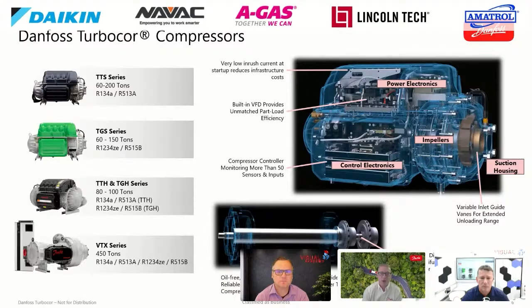Then we have the suction, with a design of twin impellers. We have power electronics on top that provide all the juice for the compressor, and control electronics on the side—this is our service side, lower voltage. You can pull that cover off, and anything that might need service or changed out in the field is available there. So it is a serviceable, rebuildable compressor if it needs to be repaired in the field.